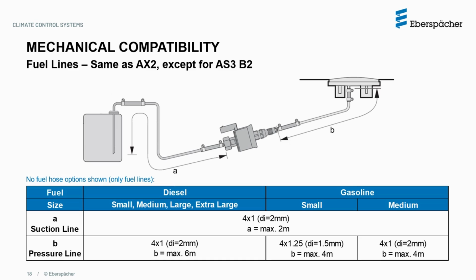Regarding fuel line diameters and length, it's the same as the second generation, with the exception of the new size gasoline small heater that must use a 4x1.25, so internal diameter of 1.5 mm, only in the pressure line, compared to a fuel line of 4x1, so internal diameter of 2, in all other sizes and fuel options. On the suction line, all AX3 heaters use the same 4x1 line.